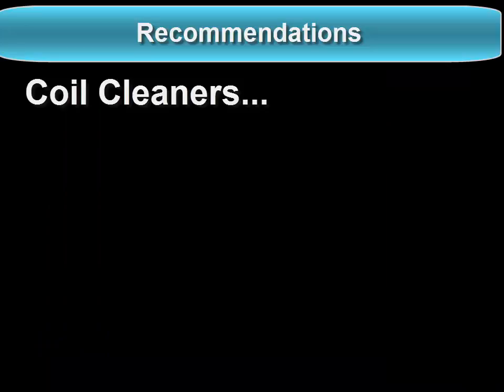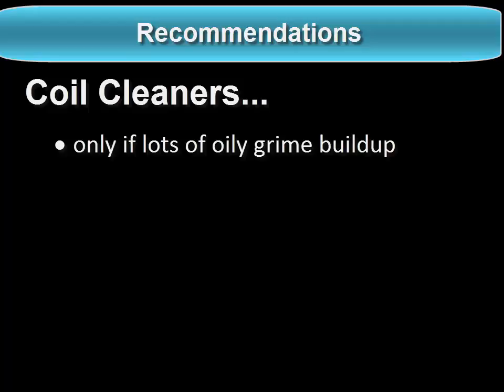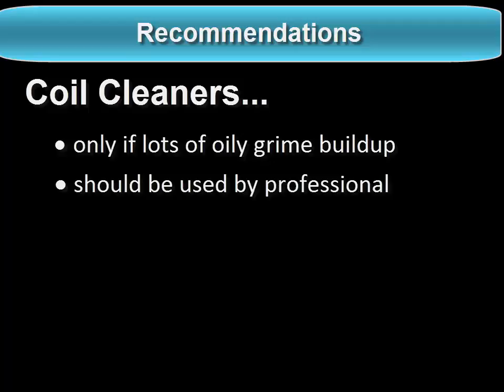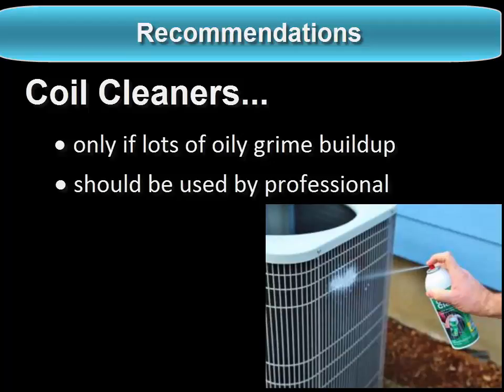Here's our recommendation on coil cleaners. We recommend coil cleaner chemicals only if you have several layers of oily grime and only if they are used by a professional. Here's why. These cleaners, especially the foaming kind, can spread into hard-to-reach areas. If they are not completely rinsed out, they can corrode the metal and damage the unit.